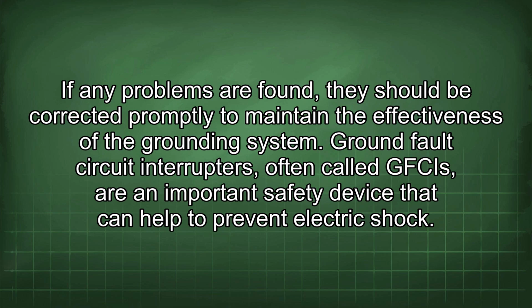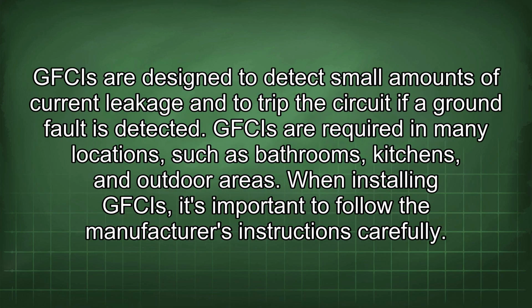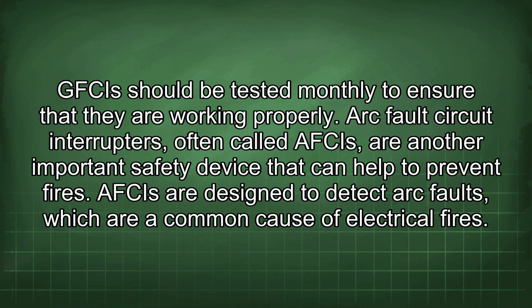Ground fault circuit interrupters, often called GFCIs, are an important safety device that can help to prevent electric shock. GFCIs are designed to detect small amounts of current leakage and to trip the circuit if a ground fault is detected. GFCIs are required in many locations, such as bathrooms, kitchens, and outdoor areas. When installing GFCIs, it's important to follow the manufacturer's instructions carefully. GFCIs should be tested monthly to ensure that they are working properly.